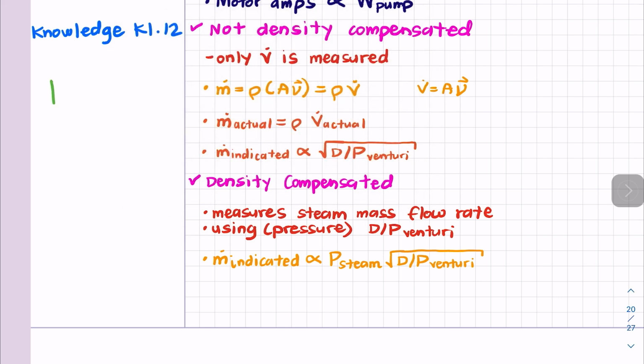So fluid temperature is going to increase. The density of the fluid is going to decrease, right? This can cause the flow meter to measure a higher flow rate than what is actually occurring. And similarly, if the temperature of the fluid does the opposite and density increases, then this decreases, right?